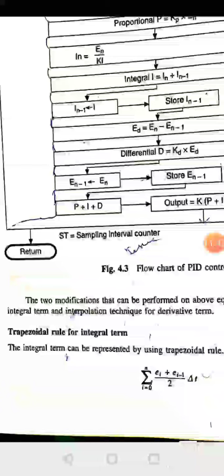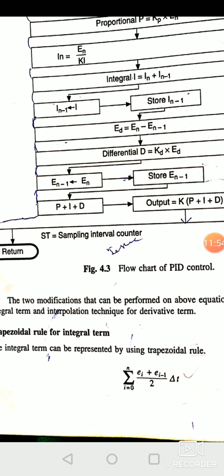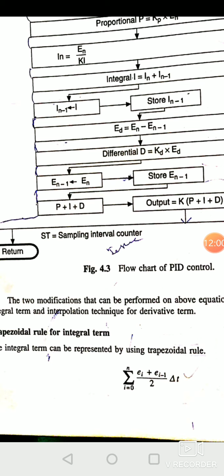Now, in order to increase the accuracy of a PID controller, we need some modification. The first modification is for the integral term. Here in the integral term we will use the trapezoidal rule, and an interpolation technique for the derivative term. First we will discuss the trapezoidal rule for the integral term. Whenever we take the value of a process output at different instants and then take its average, it will give greater accuracy as compared to a single value. That's why in the trapezoidal rule the integral term can be changed like this: i equal to 0 to n Ei plus Ei minus 1 divided by 2 delta t, or you can say we are taking the average of the error between two instants, the first instant and the previous instant. This one is the trapezoidal rule.